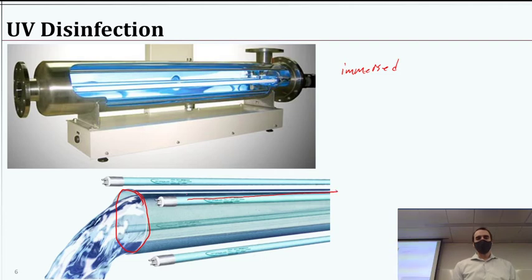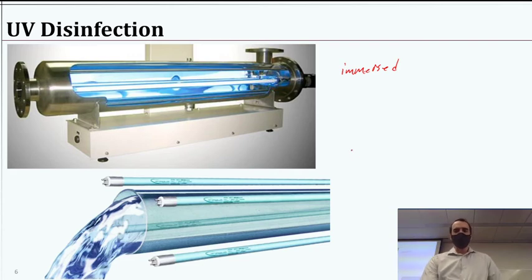In practice what this could look like, you may have a system where you have the UV light sheathed inside a quartz sheath that you can clean and let water be flowing across it and around it. That's this picture here. We've got this larger tube with waters going through it, so we call this immersed. This is actually the most typical one. So where you immerse your light into the water, you protect it with this quartz sheath. As you might imagine, that quartz is going to be pretty fragile. The light inside is also fragile and contains a toxic chemical, mercury. So there's a few factors here that you have to be careful with, which is one of the reasons that it's pretty exciting to see ultraviolet-emitting LEDs coming online.